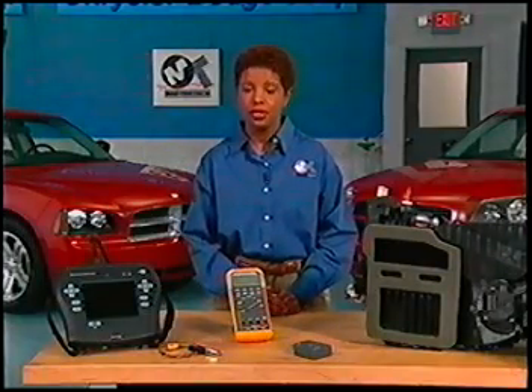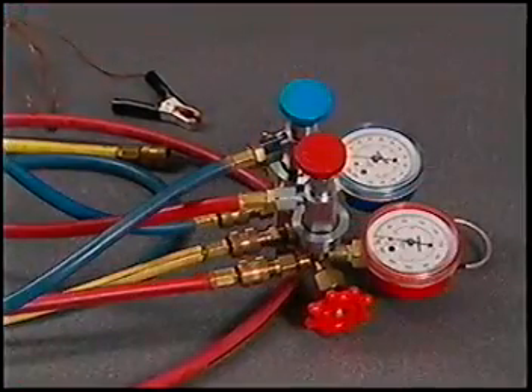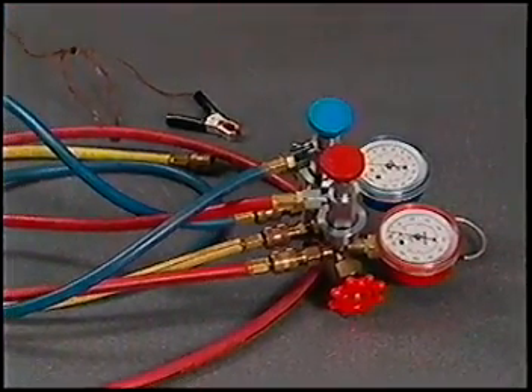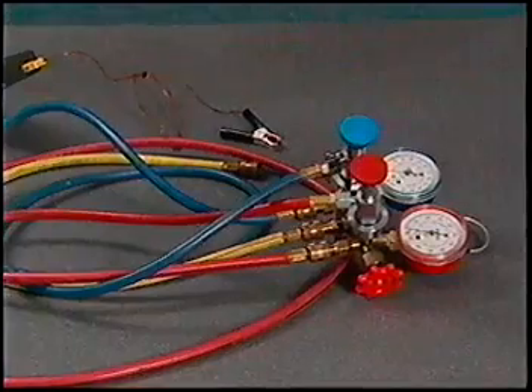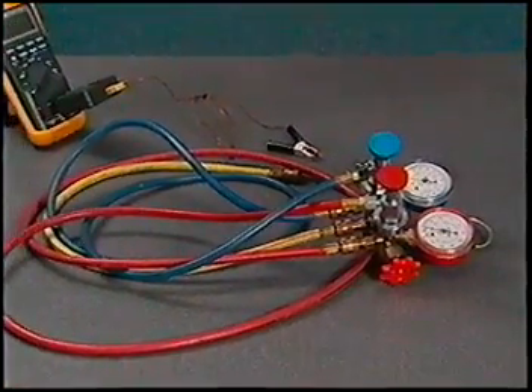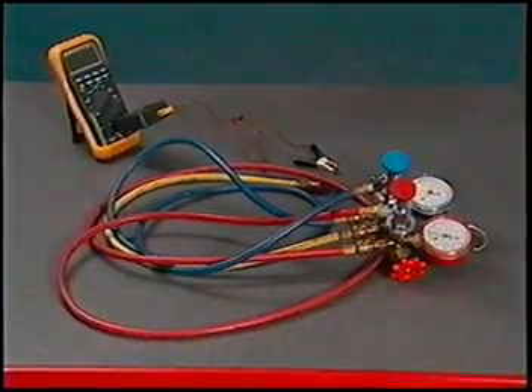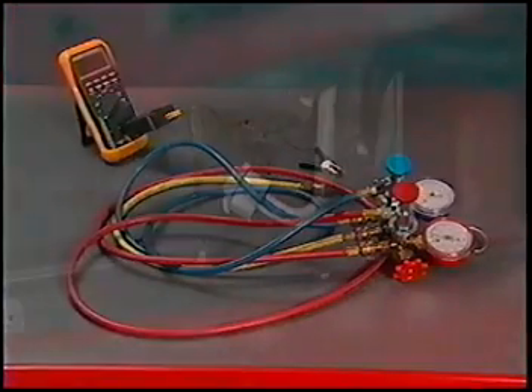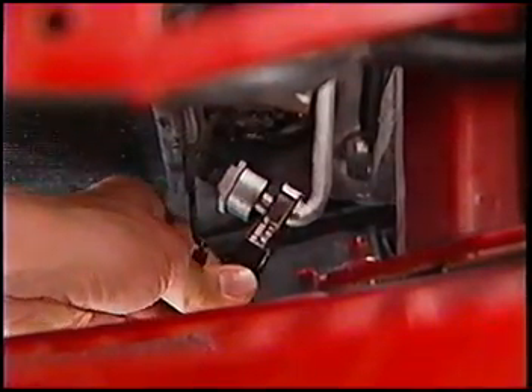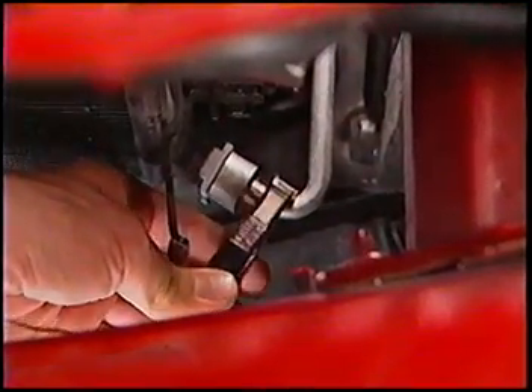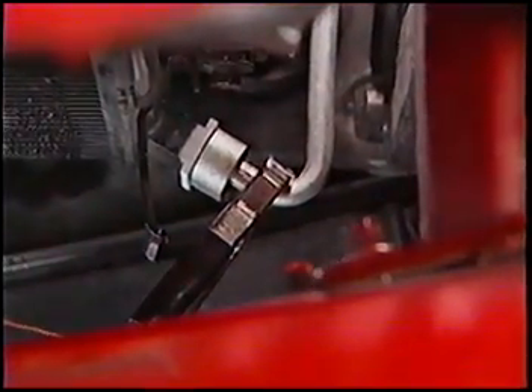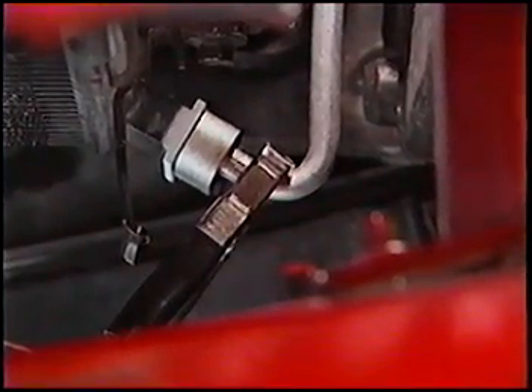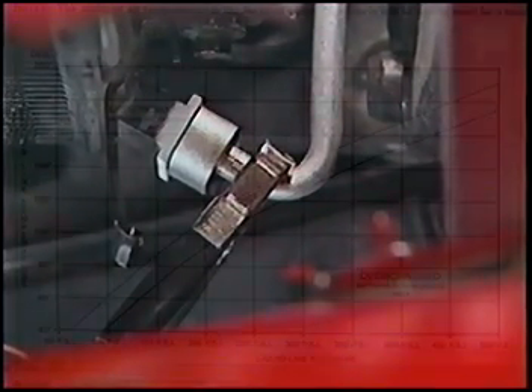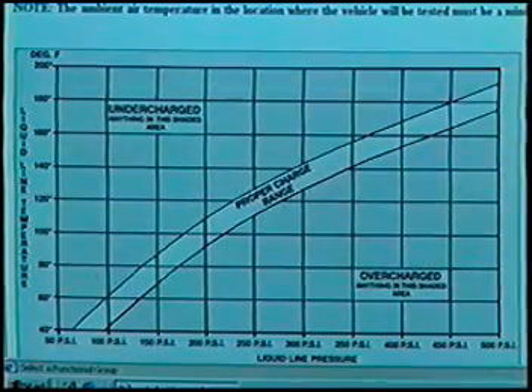To ensure accurate results, you'll need the proper tools, which include a manifold gauge set or charging station for high side pressure readings, and a digital thermometer with a clamp-on thermocouple probe for liquid line temperature. You'll also need to follow the test steps carefully. It's particularly important to place the thermocouple probe on a clean section of the liquid line as close to the condenser as possible. Where the high side pressure and liquid line temperature fall on the test chart will indicate whether the amount of refrigerant is the problem.